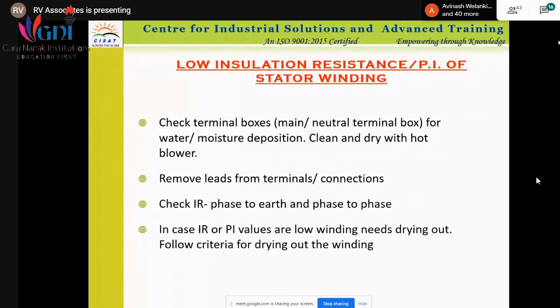Then there are various types of tests, what we call the offline tests. Like in a transformer, a tan delta test or capacitance test is important. The same thing applies to the motor. Just to check the healthiness of the motor, we take the values of tan delta, the capacitance test. Then we use the PI, polarization index test. That PI value should be within the prescribed limit. Then we do the IR test, the measurement of the insulation resistance of the winding.